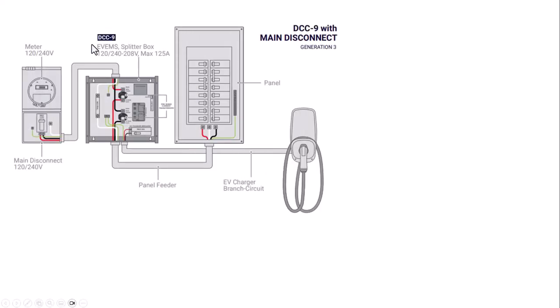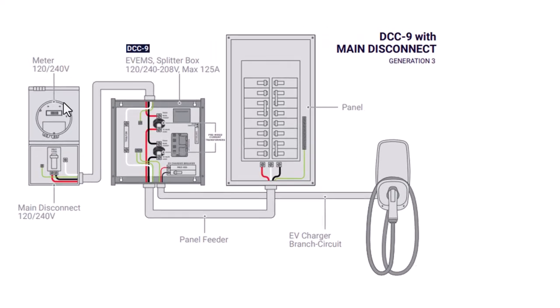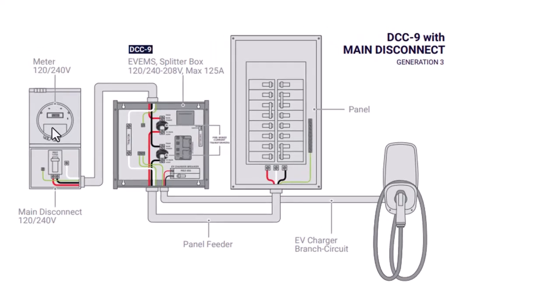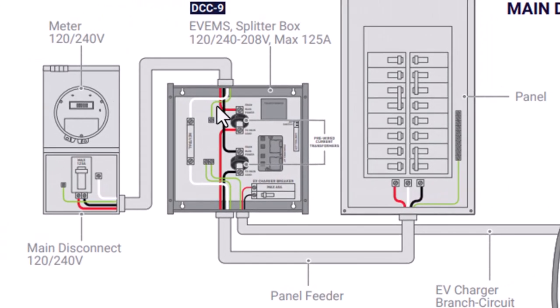So I'm going to start talking about the DCC, and I'm going to start with the DCC-9. There are actually 4 versions, a 9, 10, 11, and 12, but I'm going to start with this 9 first. If you look here, this is the DCC right here, and this is your meter. So the service comes in through the meter. It goes through the main disconnect. This is a 240 volt rated system. It goes in, and you can see a white wire, which is the neutral. You have the red, which is a 120 volt hot leg, and then you have the black, which is the other 120 volt hot leg.